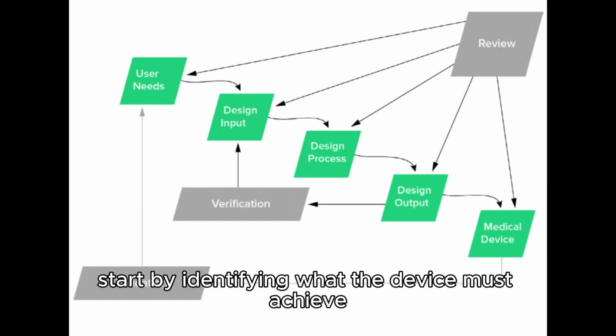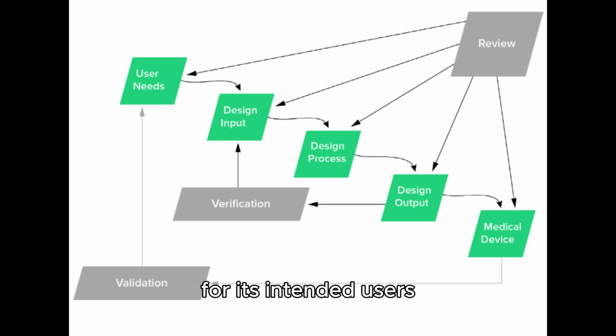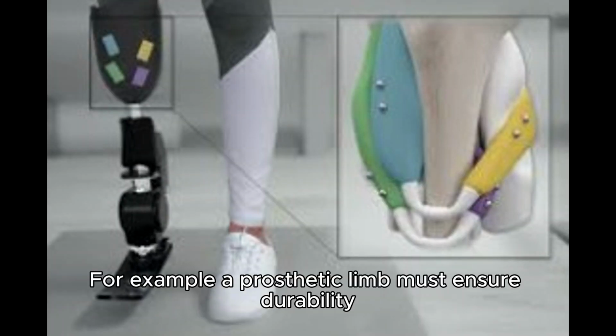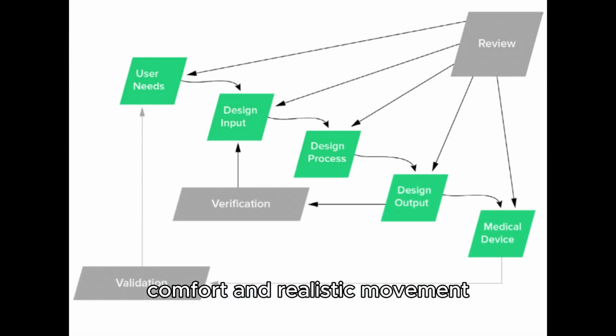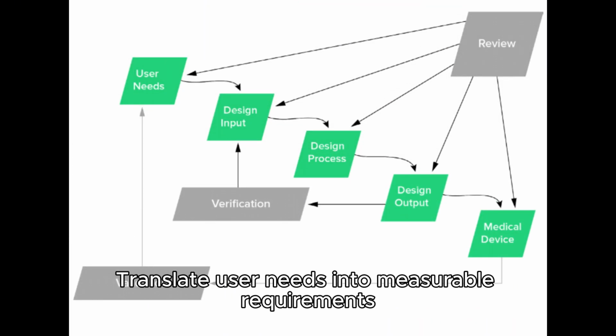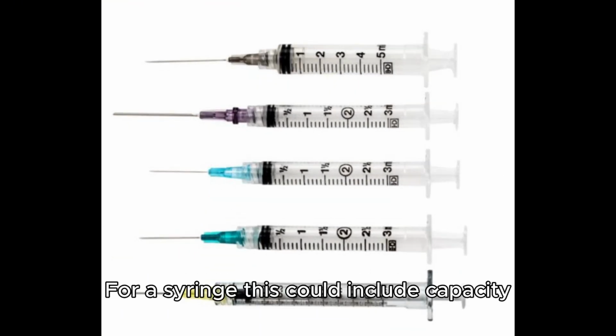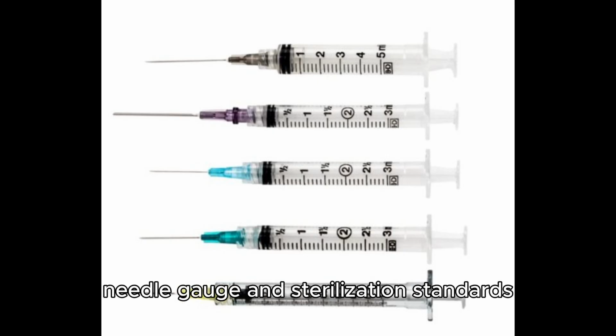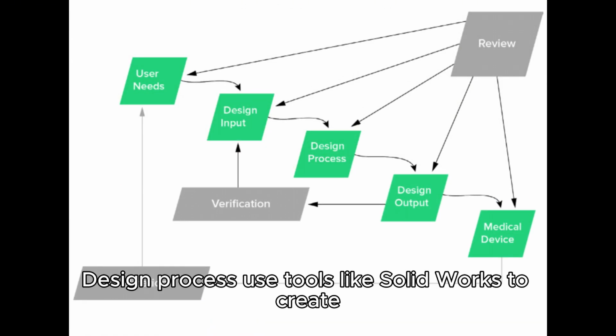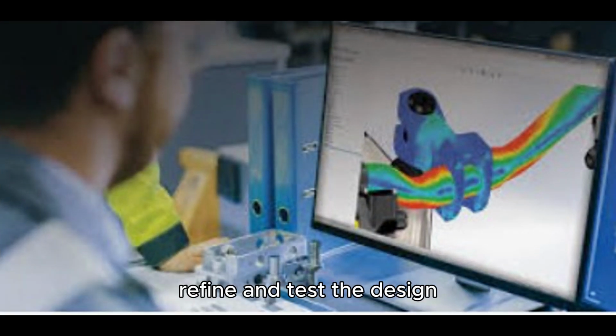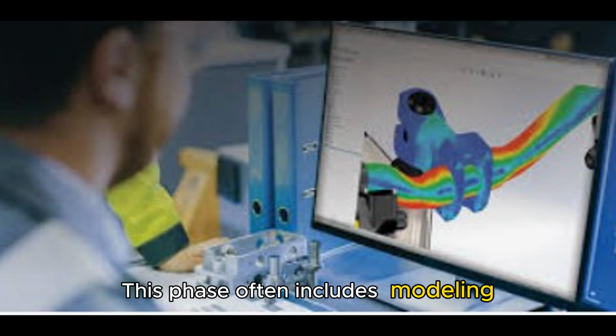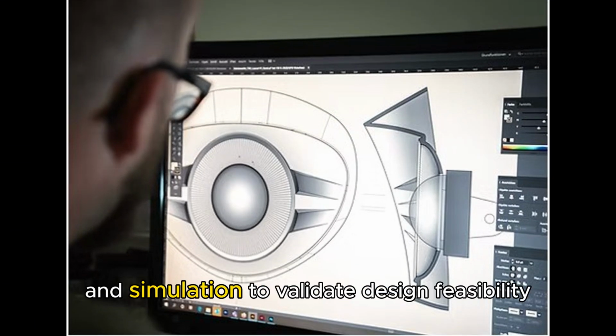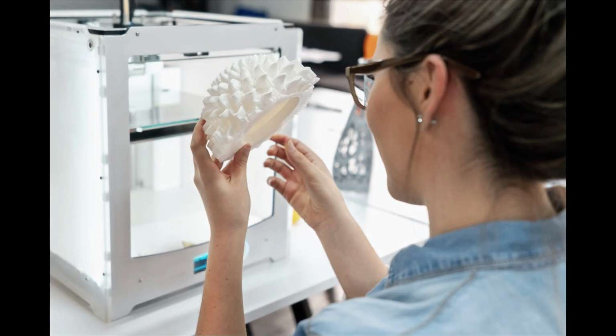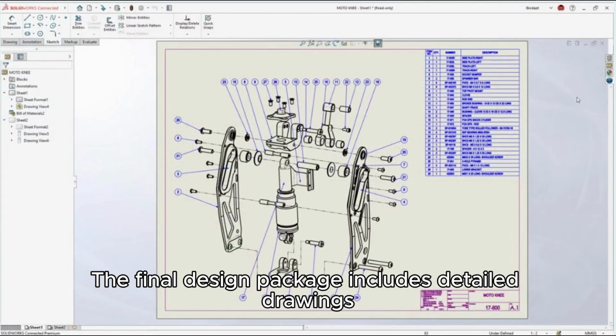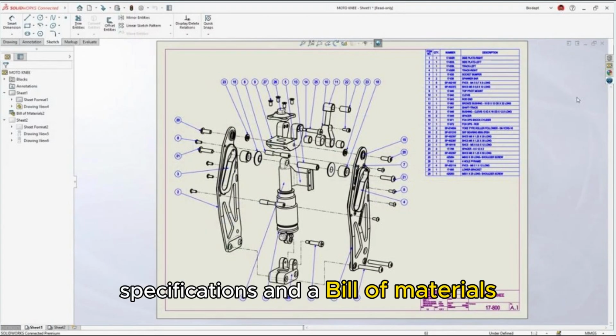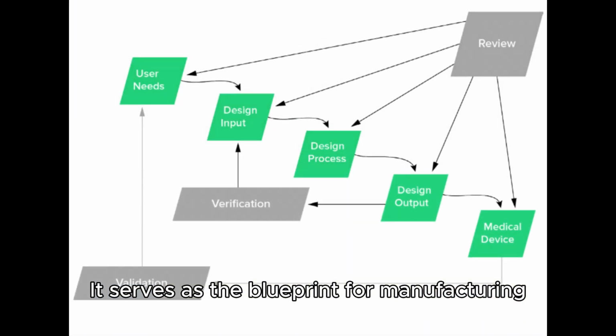User needs start by identifying what the device must achieve for its intended users. For example, a prosthetic limb must ensure durability, comfort, and realistic movement. Design input translates user needs into measurable requirements. For a syringe, this could include capacity, needle gauge, and sterilization standards. Design process, use tools like SolidWorks to create, refine, and test the design. This phase often includes CAD modeling, prototyping, and simulation to validate design feasibility. Design output, the final design package includes detailed drawings, specifications, and a bill of materials. It serves as the blueprint for manufacturing.